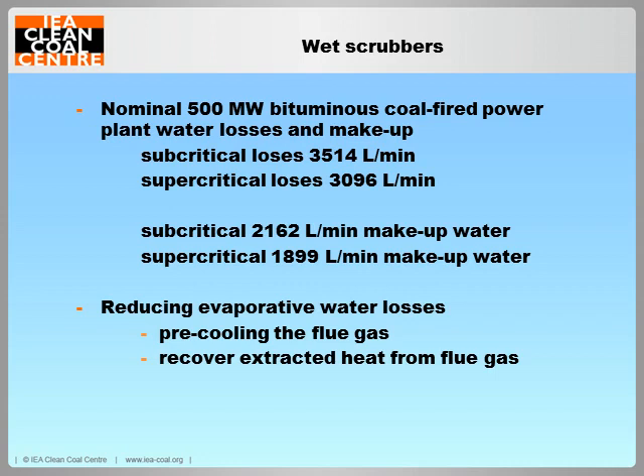Right, to give you some idea of the evaporative water losses from wet scrubbers, a 500 megawatt subcritical power plant that fires bituminous coal loses over 3,500 litres of water vapour per minute through the stack. An equivalent supercritical plant loses just over 3,000 litres a minute. So water has to be added to make up for the various water losses as indicated on this slide. So one way to reduce evaporative losses from the stack is to cool the flue gas before it enters the absorber tower. This can lower water consumption by around 40 to 50%.